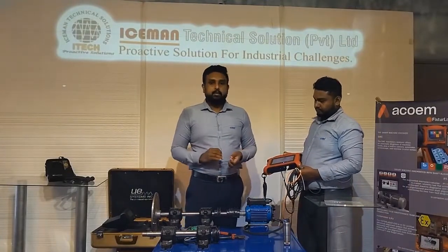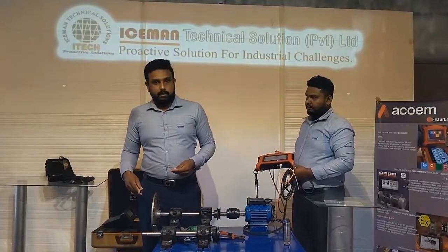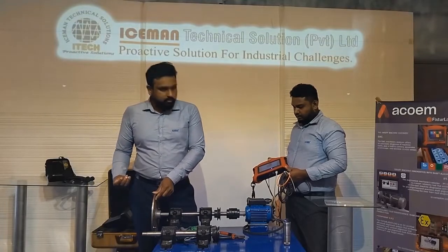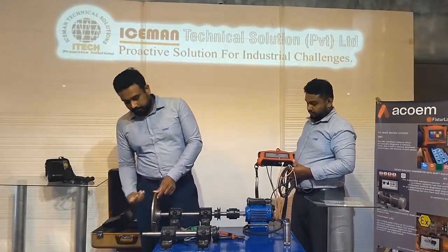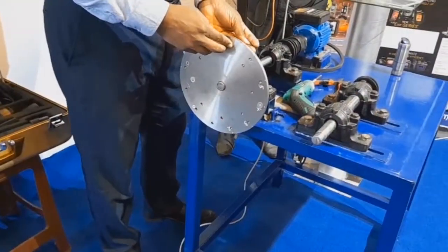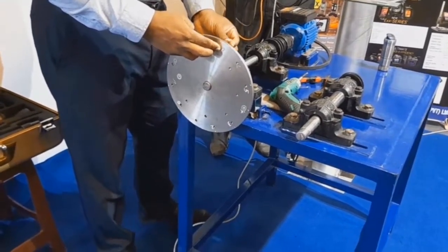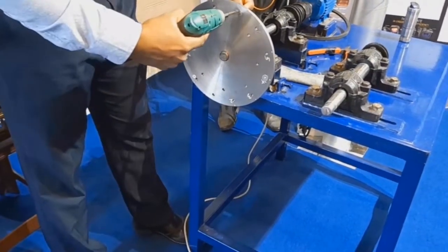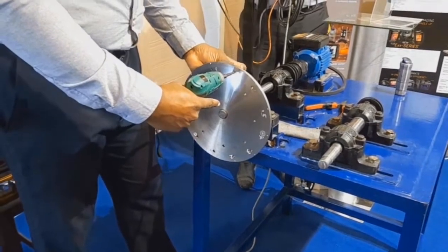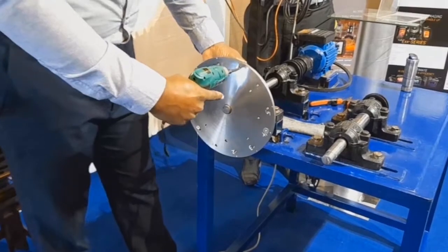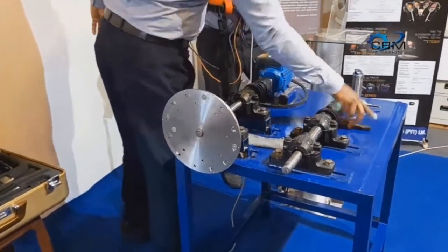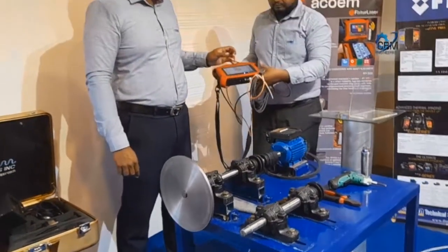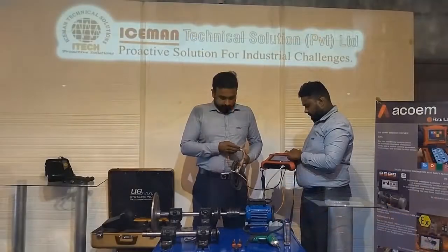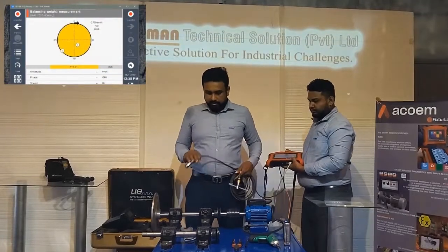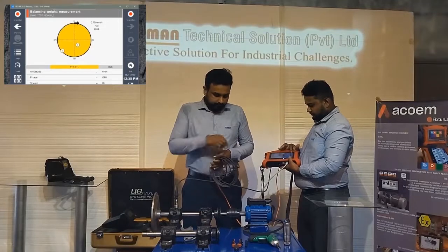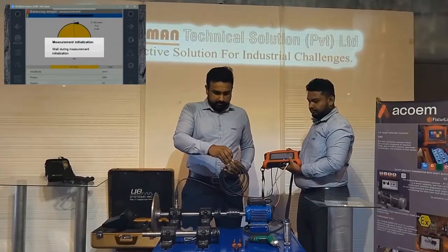So we add the same weight at the different angle given by the balancing module. You see, it gives 7.27. That means we can add at the nearest point, location 7. We will see, after adding the balancing weight, how the vibration value varies. Okay, we fix the balancing weight and we check how the vibration varies. Same as the previous, we take the vibration at the nearest point. The tachometer is the same as previous.